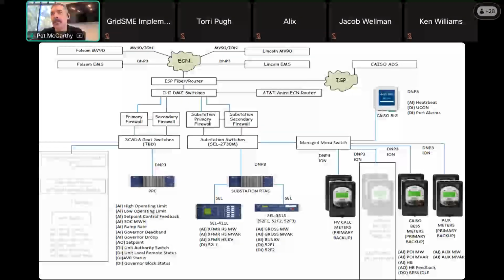So meters, relays, sometimes power plant controllers, which aggregate data from different types of devices. CAISO's expectation is that the entire data path from the originating device to the rig, and subsequently to the point map that CAISO is going to read, has been tested. So if a piece of data, like your auxiliary megawatts, passes through 5 intermediate gateways or processors or whatever, the testing should be performed from that originating device — the aux meter — all the way up to the rig. That way, anywhere that scaling, dead bands, sign conventions, or polarity could be erroneous, you'll be able to see it between the two devices.